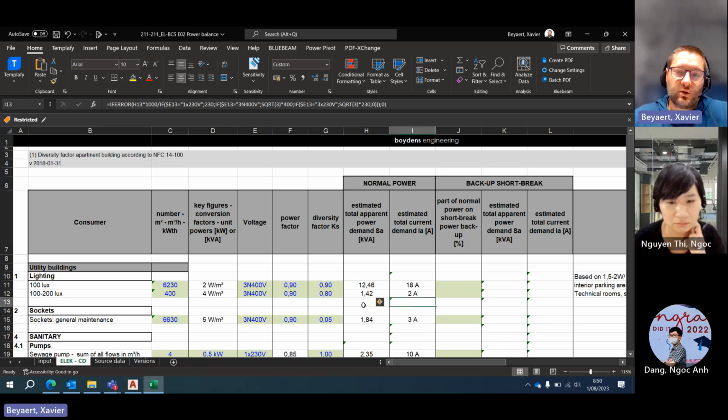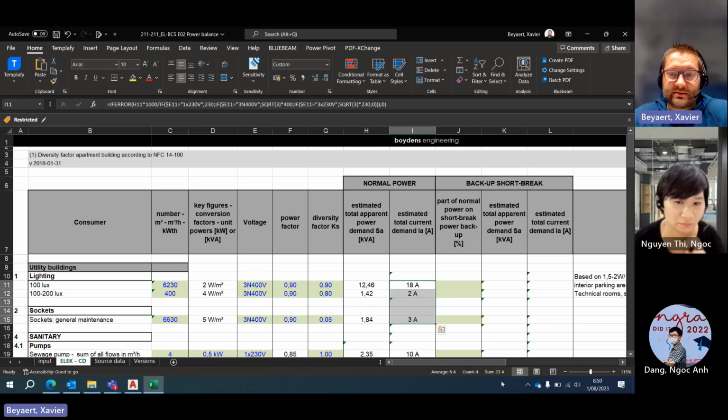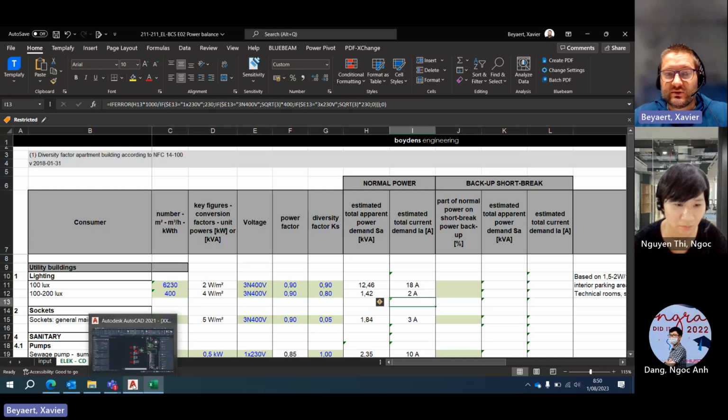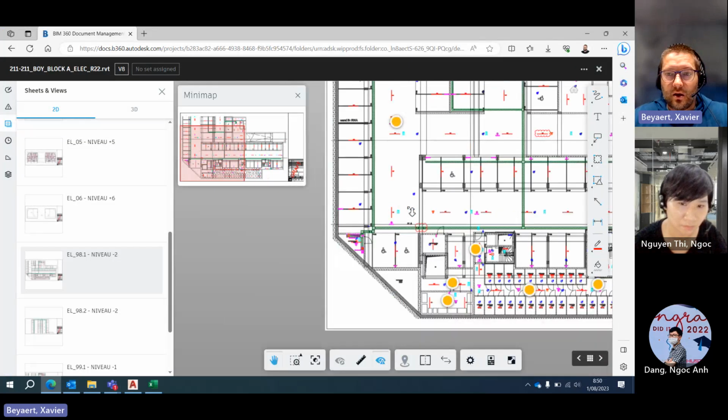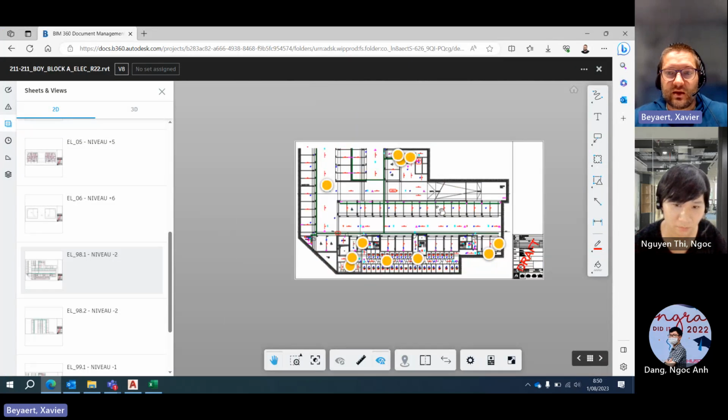Yeah, on a different one, but you will see it's just that it will be 32 amps divided by 2 because you have two levels, two panels. So you only have 16 amps for that electrical panel. But why do we do it in a separate panel? Because of the distance of the cables. Because if you stay below 60 meters, you will stay in the same section of cable.